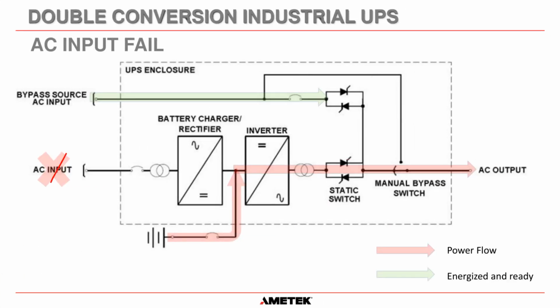And if we have a power failure on this, just like your laptop, the battery takes over seamlessly. It doesn't switch to battery. The battery just takes over seamlessly, and it's a direct connection to the inverter. It doesn't go through any DC to DC conversion. It's just a direct connection into the inverter, and the inverter changes that DC into AC and carries on going. You will not see any blip or any switching in this process whatsoever. The AC output will remain constant when you lose AC input power. Okay.